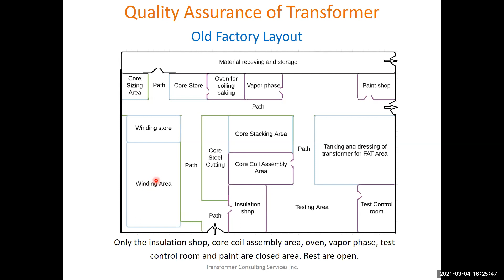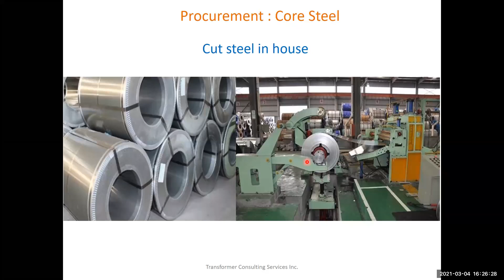When you are cutting the core steel, that means you are creating that iron filing. When you are creating that iron filing, those iron filing can fly and land between the two turns in the winding. There is no test that you can pick it up in the factory acceptance test. The transformer is not going to fail right away. Over the period in the long run, due to the dynamics inside the transformer of the oil flow and all those things, in the long run, it can cause the failure of the transformer. That means you are compromising the quality of the transformer if the factory is something like this.